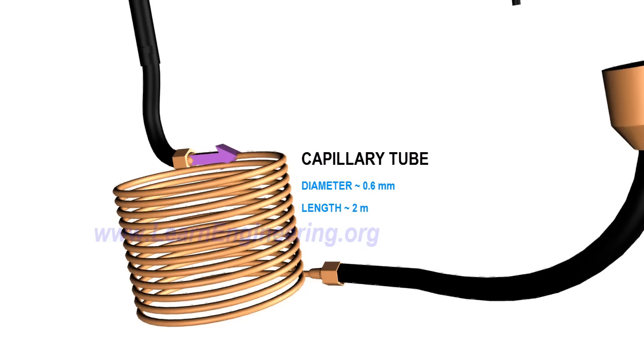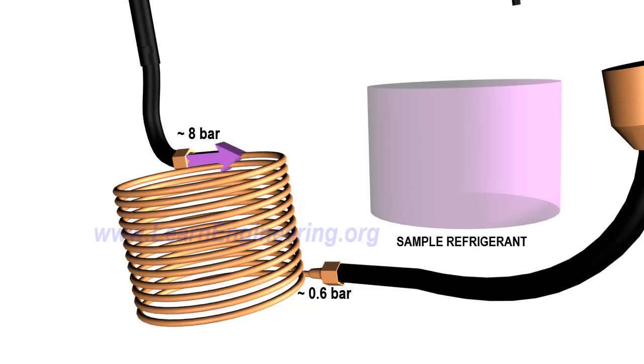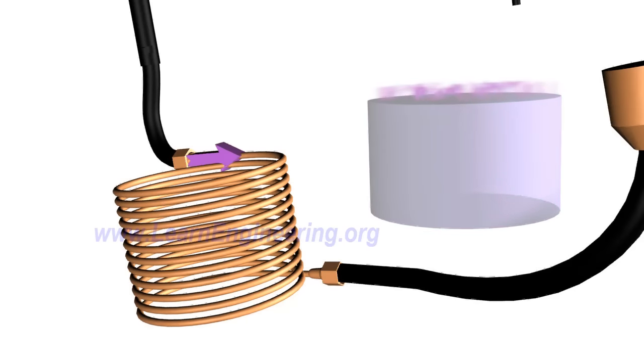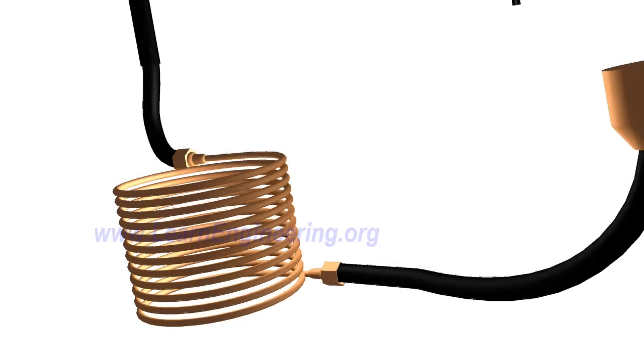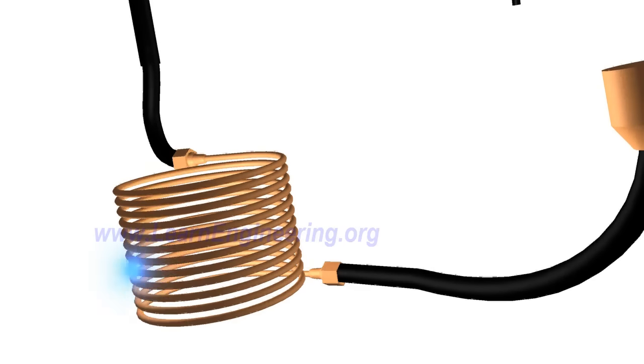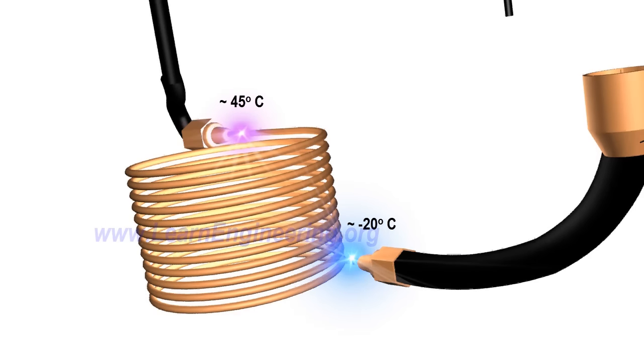The throttling device is an obstruction to the flow which causes tremendous pressure drop. Due to the drop in pressure, the boiling point of refrigerant comes down and it starts evaporating. Heat required for evaporation comes from within the refrigerant, so its temperature drops. If you check temperature across the throttling device, you can notice this drop.